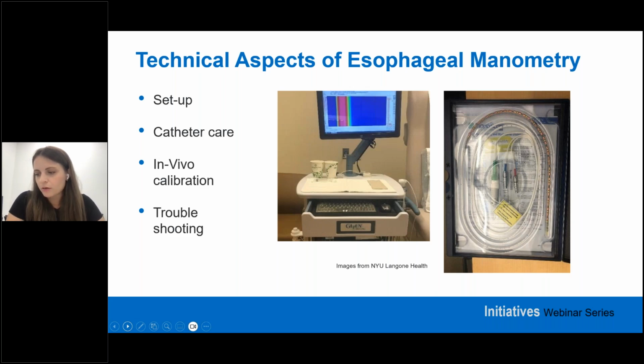One should also check that the vacuum calibration chamber is completely sealed. Sometimes if the seal is not on tight enough or there's an air leak, it will fail calibration for that reason. So going through your attachments, please make sure that there's no air leaks and everything is properly connected.